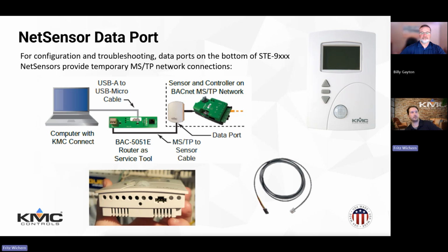So it's a way, if you're in the field and you've got that cable, you can connect in and be able to look at that trunk that you're standing next to without having to get your ladder out and get above the ceiling to try and tap into the trunk there if the router is wherever else, the other side of the building, and you don't want to walk all the way down to the IT room. Something like that, you can use that data port to be able to get in and troubleshoot that trunk from right there.